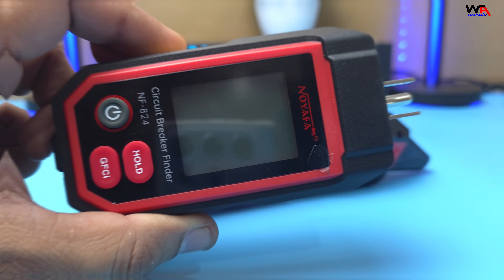Now moving to the receiver. It has a large ergonomic grip, another LCD display, an LED light for working inside dark electrical panels, and dedicated buttons for different operating modes. One feature I really like is the 7-level signal strength indicator, which helps improve accuracy while searching for the correct breaker. Another useful feature is non-contact voltage detection, allowing you to safely check whether an outlet or cable is live without making direct electrical contact.